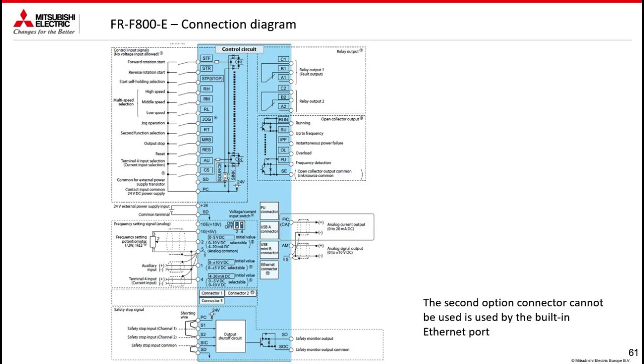As regards the signals, however, there are new ones, including STP. This signal is used for impulsive signals. Generally, the inverter works with the on state of STF to manage the gear. But if the gear is managed via buttons, it is necessary to wire STP to a normally closed button, while STF to a normally open button. So on the rising edge of the latter, the motor will start. So STP works as a self-retention.